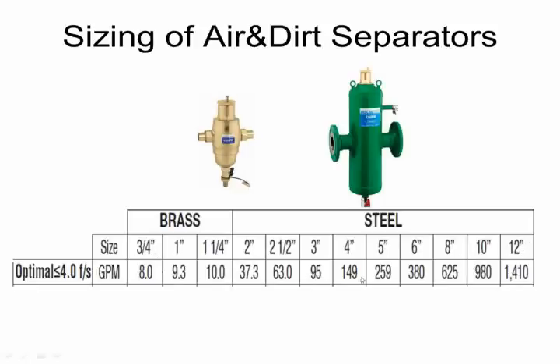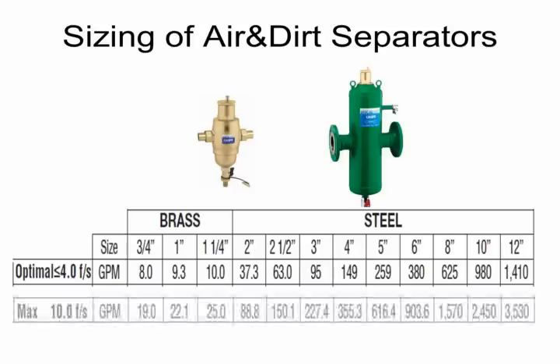So sizing separators, all of our separators, we have a quick sizing reference. So our 12-inch air and dirt separators, as an example, 10-inch, 8-inch, down to 3/4 inch, we specify a flow rate through that separator which the air and dirt elimination is most optimized, and even up to the equivalent of 10 feet per second, we indicate the flow rate, which you can take that up to. So they're high velocity rated. So as an example, our 6-inch separator can be taken up to 903.6 gallons per minute.